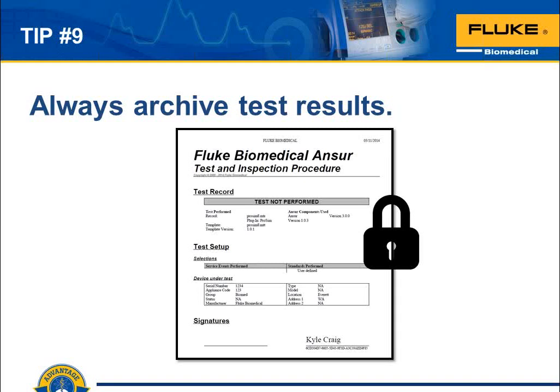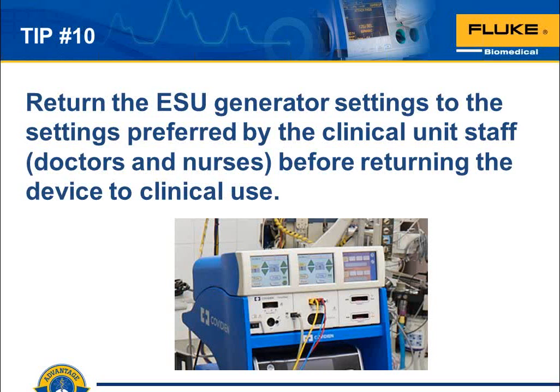The end game is what I said just a few minutes ago. Some way or another, we need to make sure that we're at least appending the automated test result reports to the CMMS work order, whether or not the interface to our automated system allows that work order to be automatically closed on the strength of an overall pass of the medical device. There's a lot of efficiencies that can be built in here, but the bottom line is make sure those test results are attached to that work order and that you can see what they are, and that somebody's looking at the longer term trend one way or another.